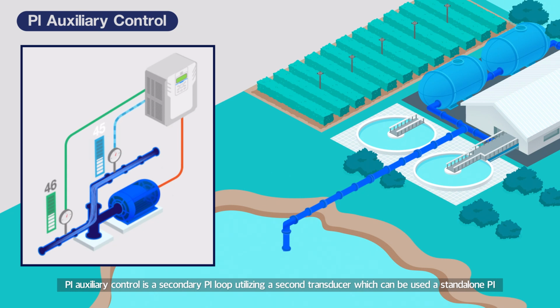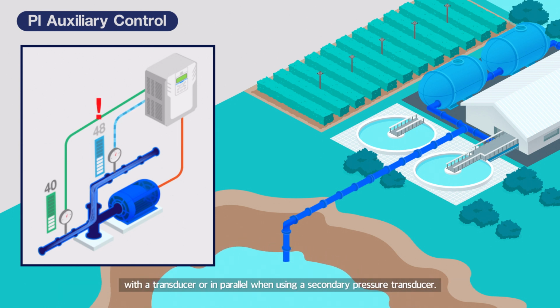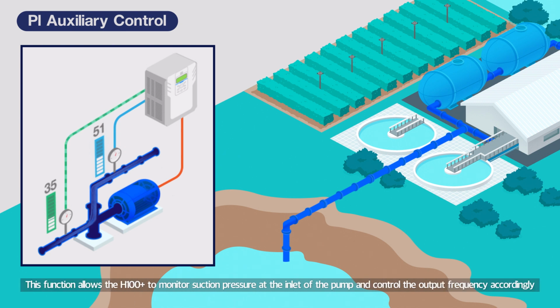PI auxiliary control is a secondary PI loop utilizing a second transducer, which can be used as a standalone PI with a transducer or in parallel when using a secondary pressure transducer. This function allows the H100 Plus to monitor suction pressure at the inlet of the pump and control the output frequency accordingly.